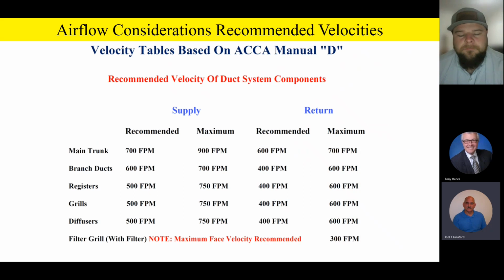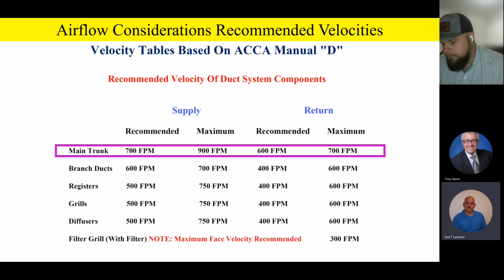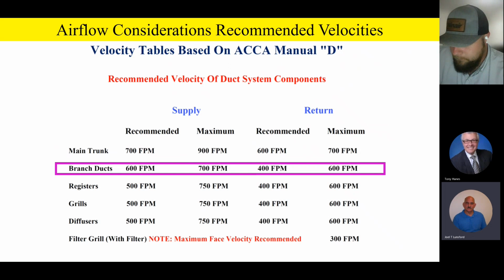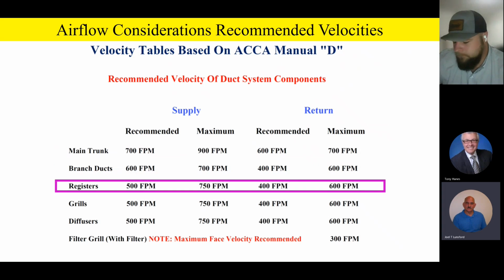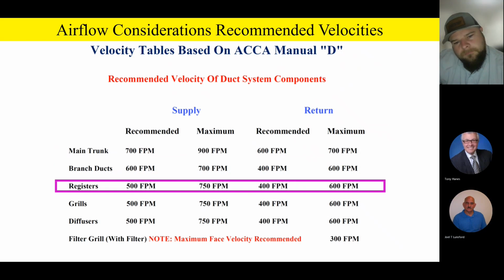And then another thing we always want to make sure of as far as the airflow is concerned, Daniel, is we want to get in there and take a look at our velocities. Even though we can have CFM, we want to make sure that we're pushing that air through the ductwork and through the duct components at the proper velocity. To give an example, on a main trunk, Manual D recommends 700 feet a minute velocity, and that's where I normally design my ductwork on my main trunks. And then my branch runs, I design them for 600 feet per minute. All of our registers and grills are going to be supplies at 500 feet a minute. Supply is recommended, and on return grills, 400 feet a minute on the return registers and supply registers.